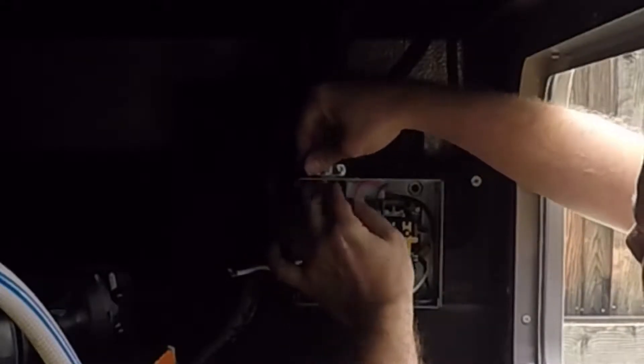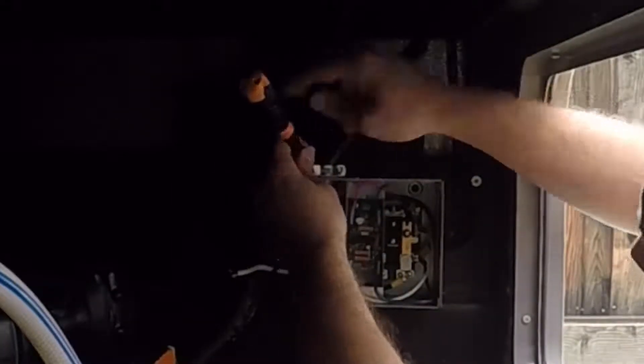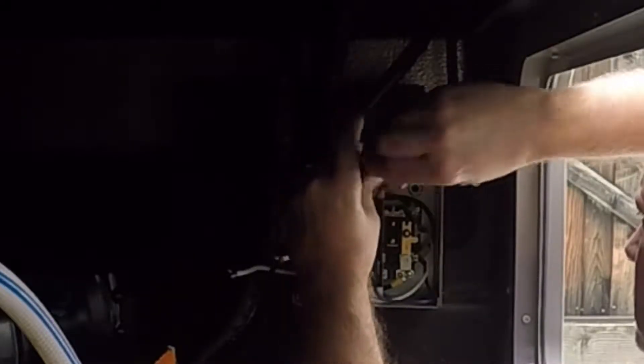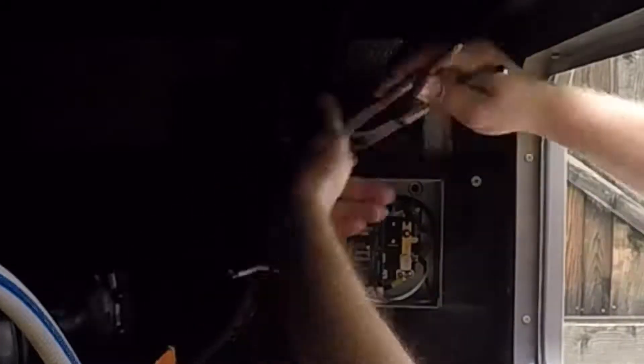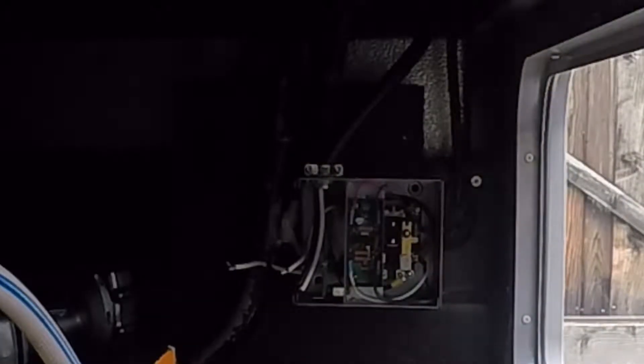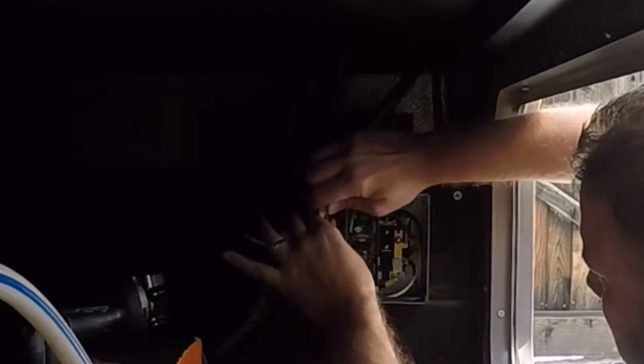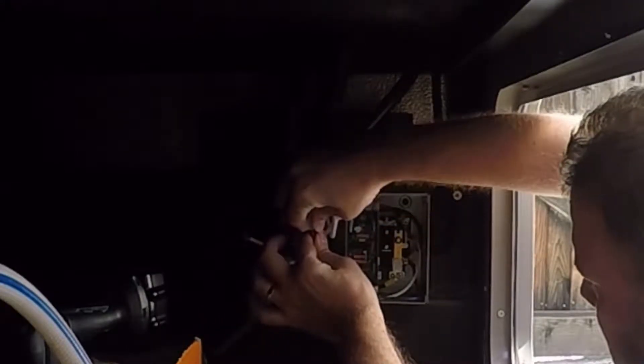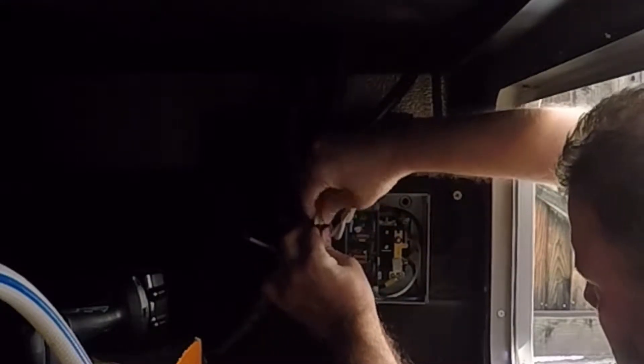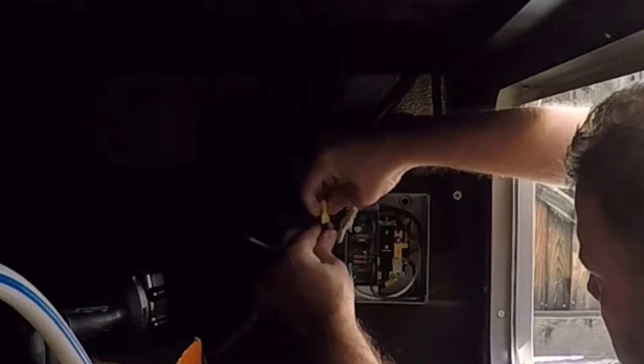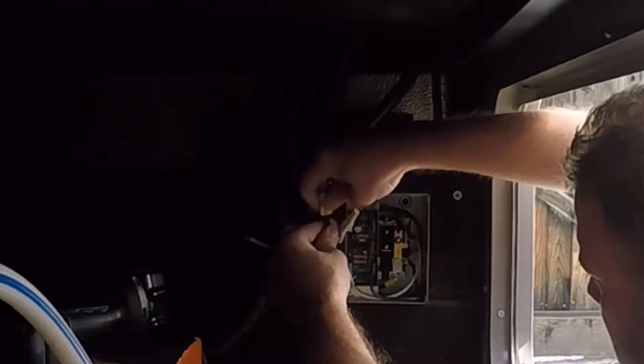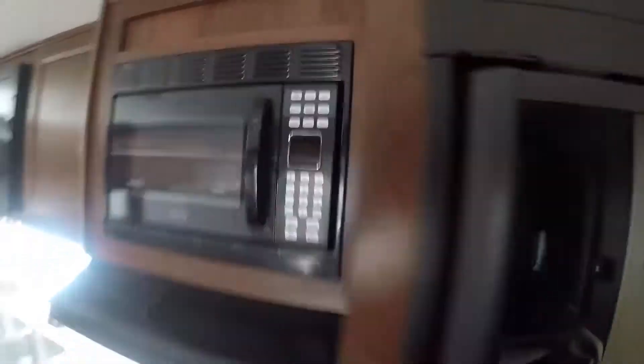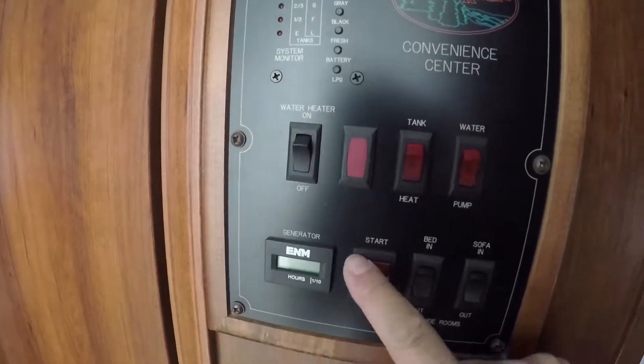The automatic transfer switch has a time delay, 45 seconds right around there, where it allows your generator to stabilize before it throws a load to it. If you were plugged in the pedestal and you wanted to fire up your generator and use it for a little bit for some reason, you don't have to run out and unplug your cord. It doesn't cause any problems. It will transfer over.